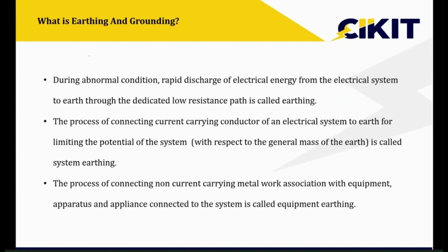So the second important component is the earthing. Earthing is nothing but the process of providing a dedicated low resistance path for the fault current or any abnormal current to discharge. So here we are providing a dedicated path so that the lightning current or other current won't flow through the body itself. The main thing is we have to provide a dedicated, low resistance path for this current to discharge. In normal cases, there won't be any current flowing through it. Only during abnormal conditions or lightning conditions alone will the current flow through this earthing.